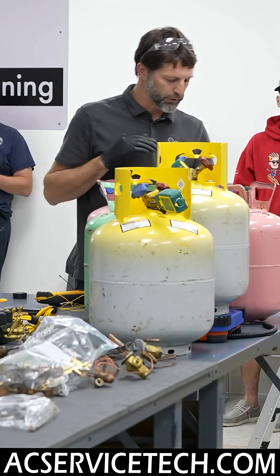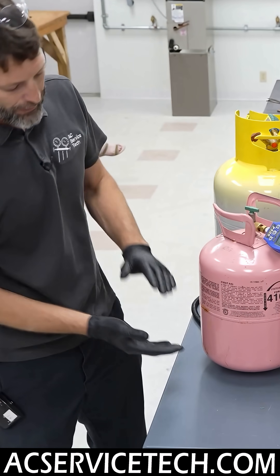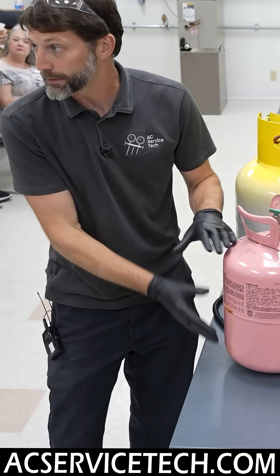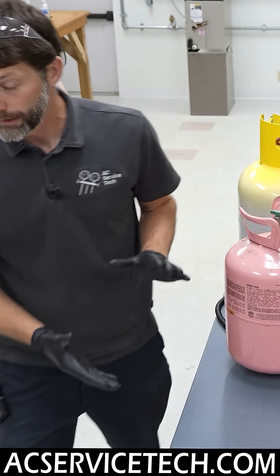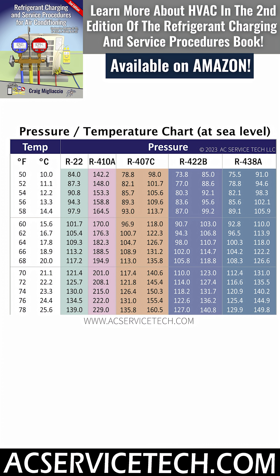What I want to go over is on your PT chart: anytime that you have a liquid and vapor in a tank, it's saturated. And if it's saturated, if we know the temperature of the refrigerant in the tank, we'll know the pressure. Vice versa, if we know the pressure, we'll know the temperature.